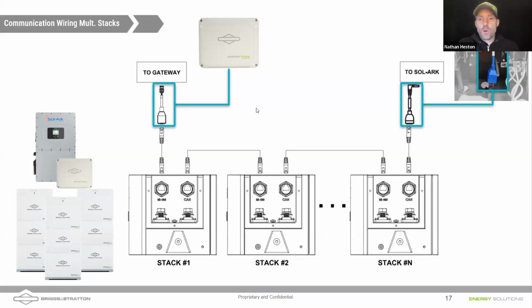I am showing here, if you are doing multiple batteries together with a Sol-Ark, you would connect those, you daisy chain those batteries in this fashion. So again, you'll get a copy of these slides. The communications that are here allows all of those batteries to work together as a single bank, and you would still need a combiner here to bring this DC power into a combiner if we have 3 or more stackable batteries.